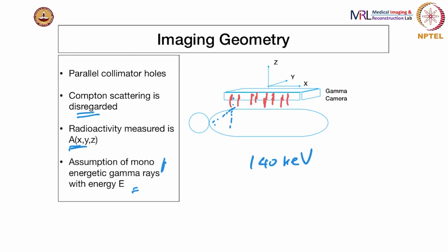Let me just wipe this out and draw it on the other side so that it's easy. So if you have a collimator here, and a bunch of radioactive compounds here, maybe different concentration, maybe same, it doesn't matter. The scintillator is here, and then the photodiodes or photomultiplier tubes are here. So the signal you will get is restricted by this collimator to this projection on the body.